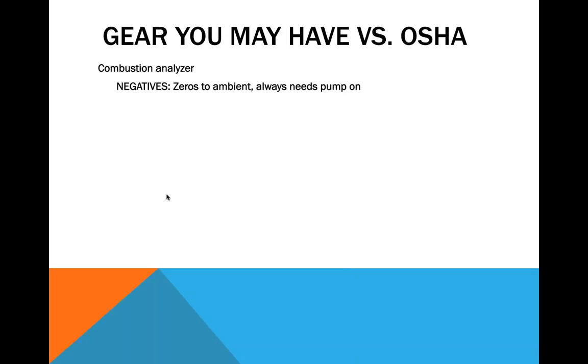You have a combustion analyzer. It has an oxygen and a CO sensor on it. So why couldn't you use it for personal monitoring in a confined space? Well, carbon monoxide analyzers zero out the CO sensor and "zero out" the oxygen sensor to the ambient condition when you power them up. So if there is CO present or an oxygen depletion, the analyzer won't know it because it's referencing to the atmosphere you're powering it up in.